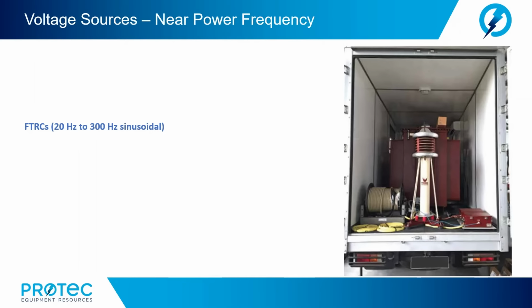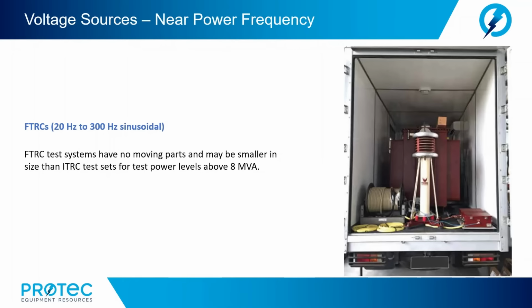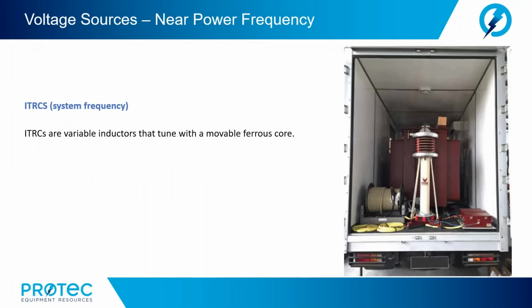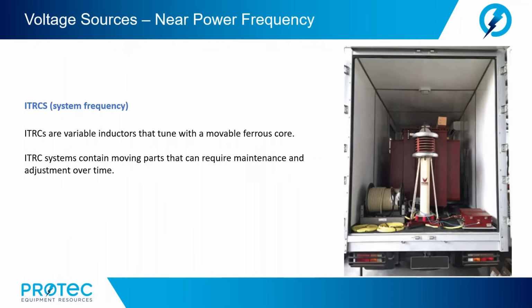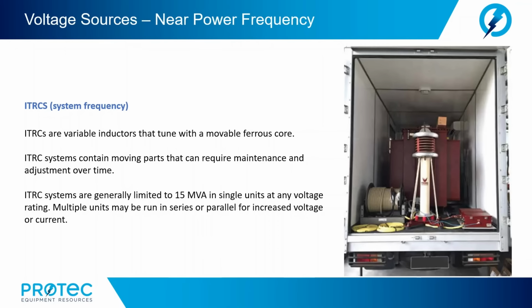So let's first look at the frequency-tuned. These are the 20 Hz to 300 Hz sinusoidal test sets. FTRC test systems have no moving parts and may be smaller in size than the inductively tuned resonant circuit test sets for power levels above 8 MVA. The inductively tuned resonant circuits are variable inductors that tune with a movable ferrous core. Now, the ITRC systems contain moving parts that can require maintenance and adjustment over time. ITRC systems are generally limited to 15 MVA in single units at any voltage rating. Multiple units may be run in series or parallel for increasing of voltage and/or current.